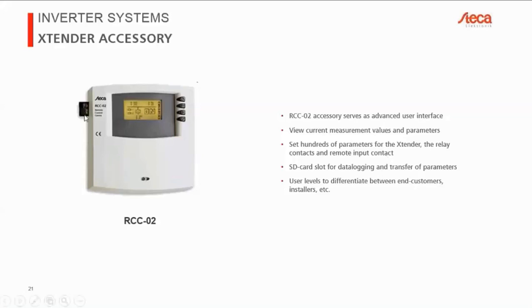The RCC02 also has an SD card slot, which is the black part you see on the left here. When you insert an SD card, you can use it either for data logging, so once a minute all of the data is logged. Alternatively, you can use it to save your parameters, or to upload or download your parameters to the SD card. So if you're using, for example, a certain type of battery, you can set up all of your parameters, save them to SD card, go to the next device, then copy all the data across.